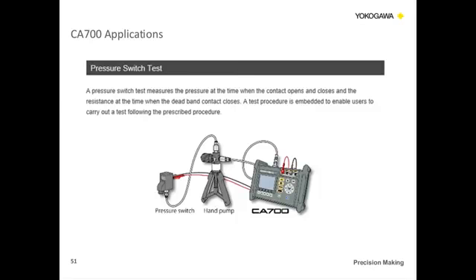Pressure switch test, Tay mentioned earlier, this unit has the capability to calculate the deadband error on a pressure switch. Basically, we pressurize the switch up to the upper limit. Once it reaches the upper limit, of course, the contactor's open. We take a resistance measurement and a pressure measurement simultaneously. We then bleed the switch back down to the low side, the contactors close, and we take another resistance measurement and pressure measurement, and then we give you the actual deadband of that switch. So this makes a lot of the testing a whole lot easier, faster and simpler.